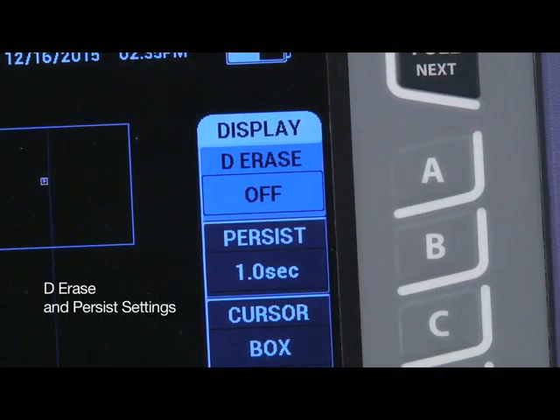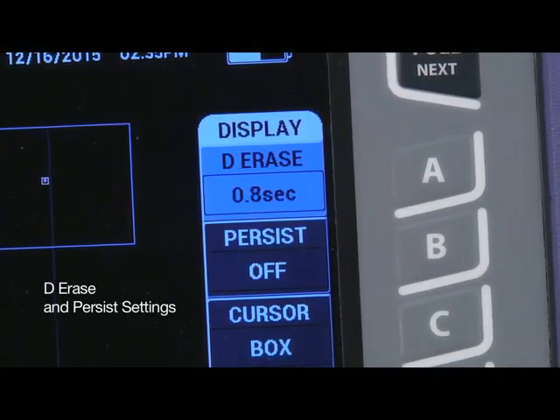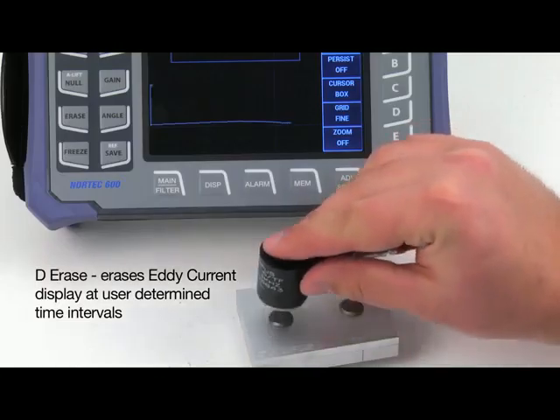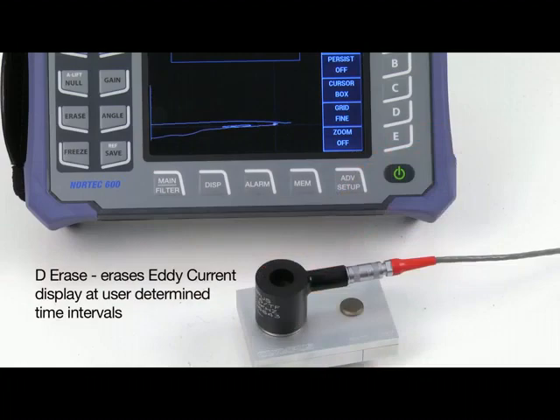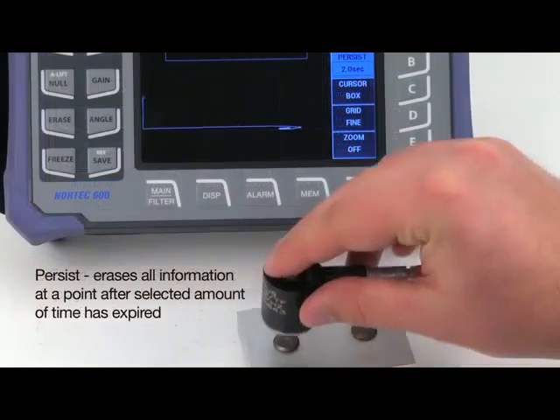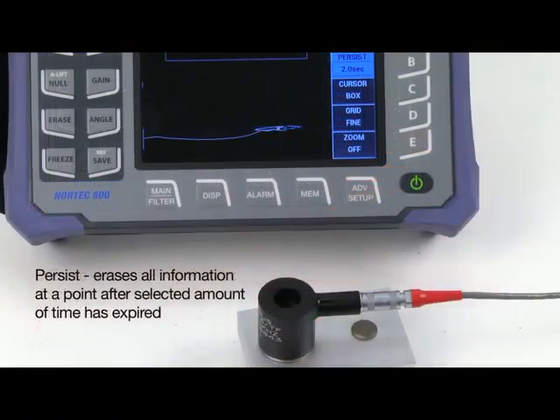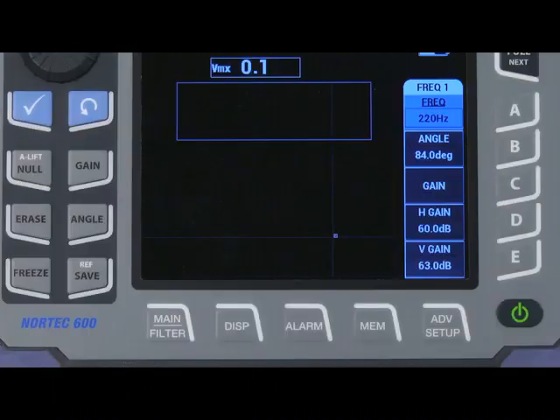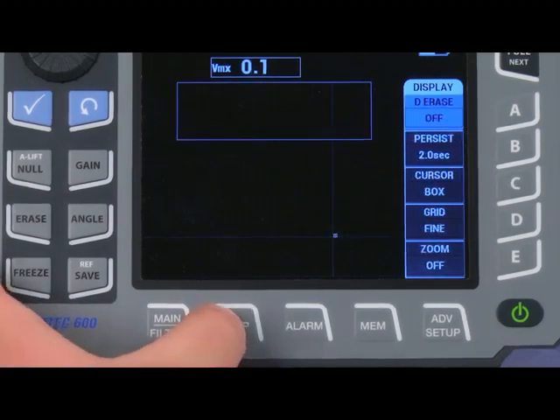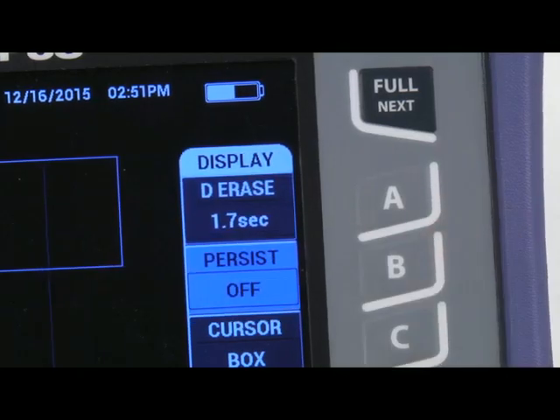Changing D Erase and persist settings can be useful for some applications. D Erase erases the eddy current display at user-determined time intervals. Persist erases all information at a particular point after the selected amount of time has expired. To set the D Erase and persist time intervals, press DISP twice, then use the A and B keys and knob to adjust the values.